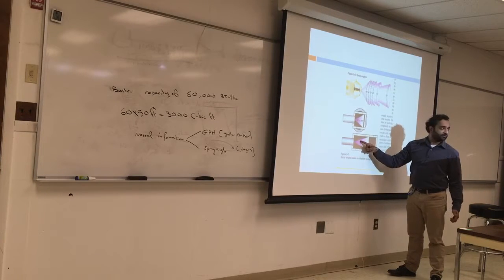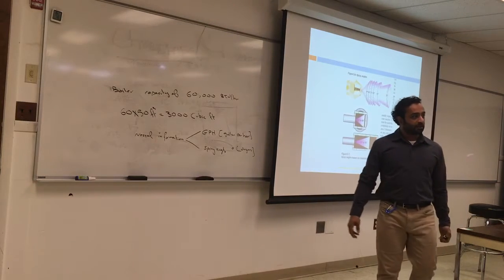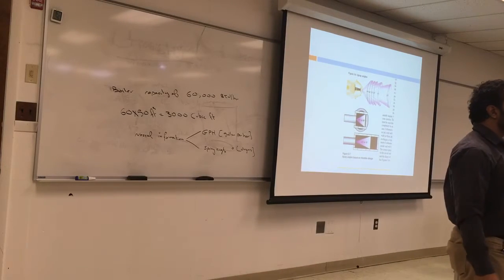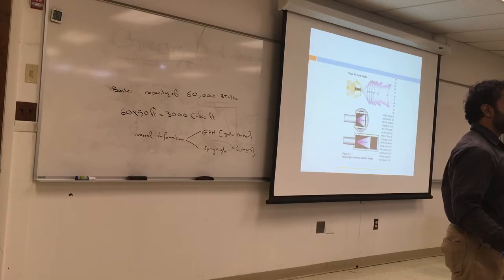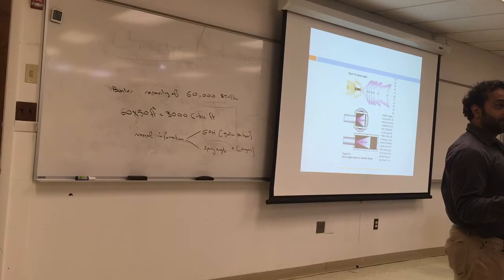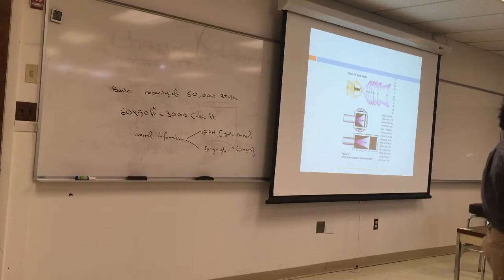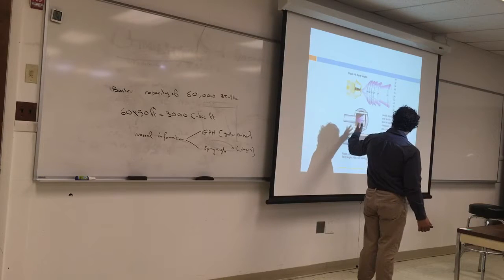Look at the chamber. There are different chambers. Some of them are long, some of them are small. And what do we not want to do? We don't want the flame to touch. Because if it touches, what will happen? Soot. You'll start having more smoke, and you'll have incomplete combustion. You'll have carbon monoxide, and you might also overheat one side of the chamber, and that will cause it to crack.